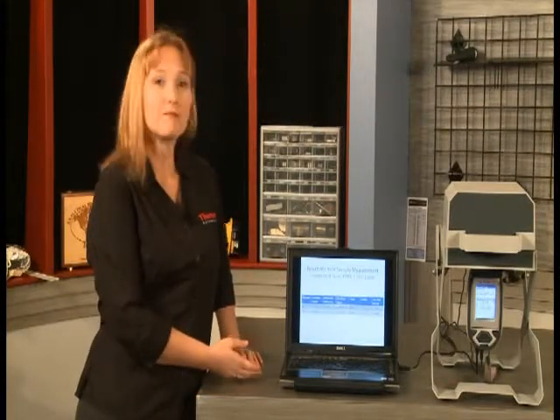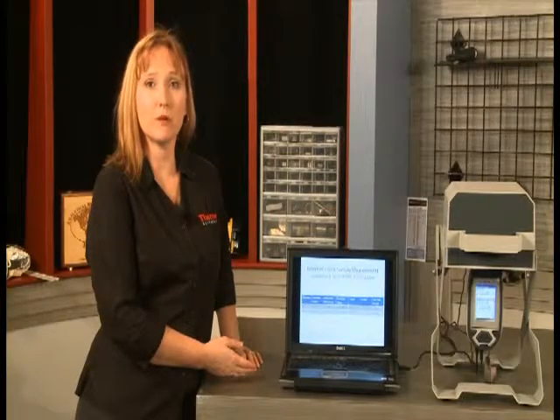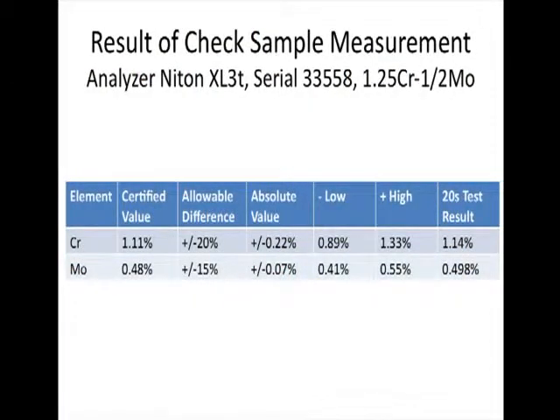We've entered the reference sample results into this table. This is from the last measurement. This will allow us to provide an example of the measurement results. We see, for example, the element chrome is certified at 1.11%, whereas our test result is 1.14%. However, when we consider the 20% allowable deviation from certified value, or multiply the 1.11 by 0.2, we get approximately 0.22% allowable deviation. This value is added and subtracted to the certified value, which gives us a measured reading lower limit of 0.89% and an upper limit of 1.33%. Our chrome reading of 1.14 falls within this range.